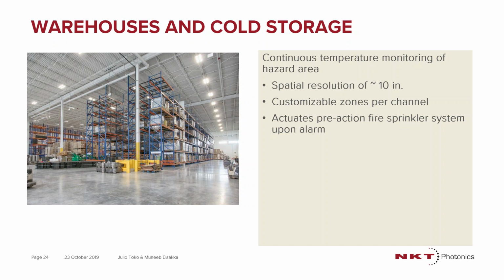But really the beauty is, you look at the system, it gives you first temperature sensing on the cold storage area in the warehouse. You know exactly how the warehouse is being cooled down, but you also have an idea of where exactly, if a fire starts, how to flood the area and how to use the sprinkler system.